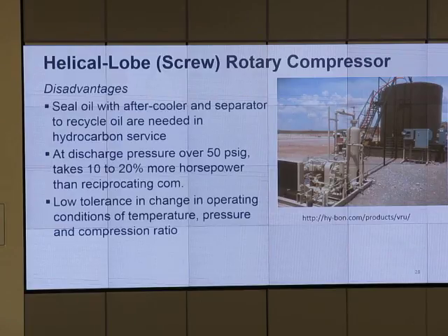So what do we do if there is not enough pressure? Anyone remember? What did you say, Victor? Recirculate gas. Yes. So they keep it running. If there is not enough gas, we take the gas that we produce or compress and send it back again, keeping it rotating or recycling. If we don't do that, it will pull vacuum on the tank and the tank will implode. So it has to recirculate. We don't turn it off, turn it on, turn it off, turn it on.